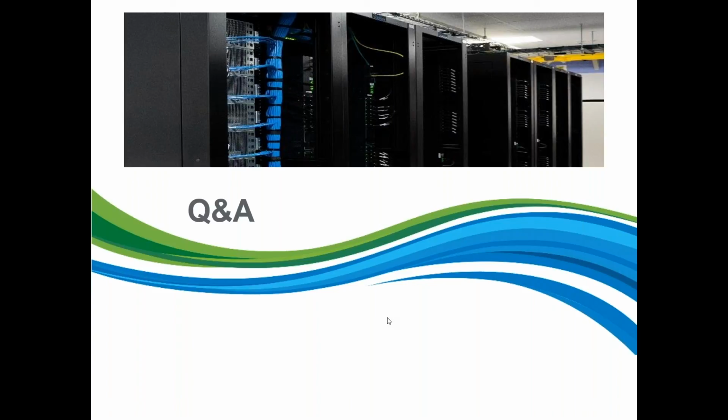I don't want to marginalize the cost. I don't want to say it's cheap, but it can be done at the main panel or the UPS. There's ways and means of doing that. And a lot of times for those embedded data centers, there's a compact number of CRAC units where you can do individual metering to get a handle on the overall critical cooling system. But for the most part, if you're going to calculate the PUE, or power utilization effectiveness, you're going to want to do it right at the power input of that data center, and it is a very, very good idea to do so.